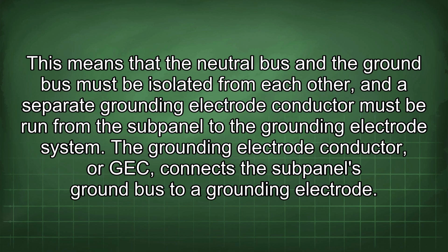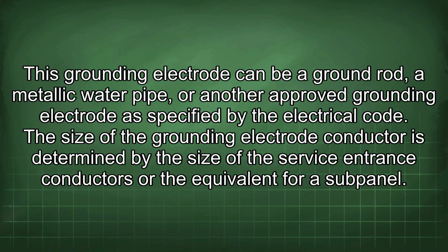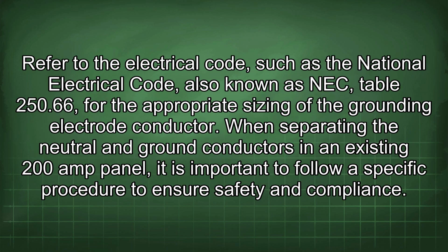The grounding electrode conductor, or GEC, connects the subpanel's ground bus to a grounding electrode. This grounding electrode can be a ground rod, a metallic water pipe, or another approved grounding electrode as specified by the electrical code. The size of the grounding electrode conductor is determined by the size of the service entrance conductors or the equivalent for a subpanel. Refer to the electrical code, such as the National Electrical Code, also known as NEC Table 250.66, for the appropriate sizing of the grounding electrode conductor.